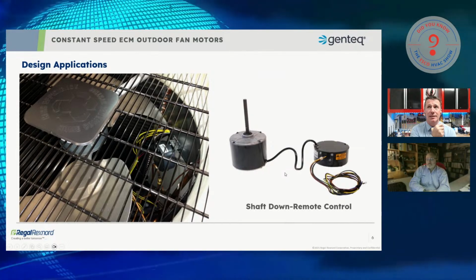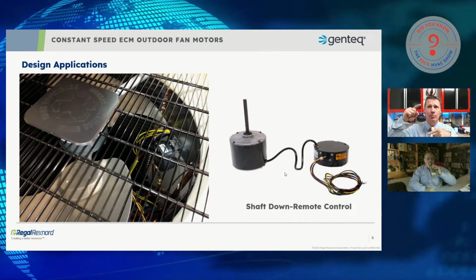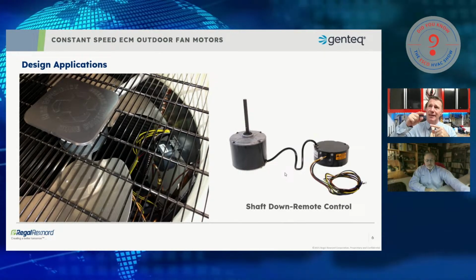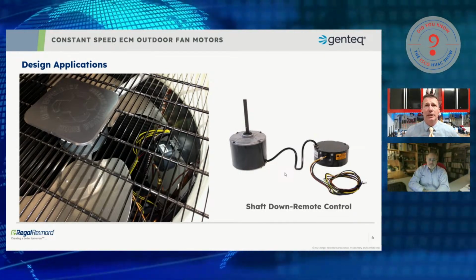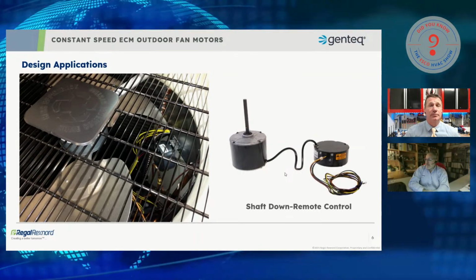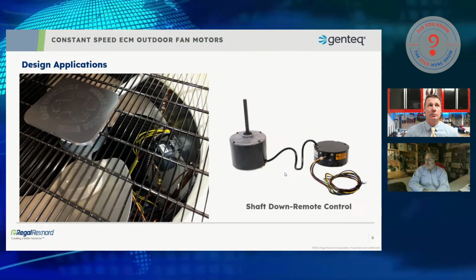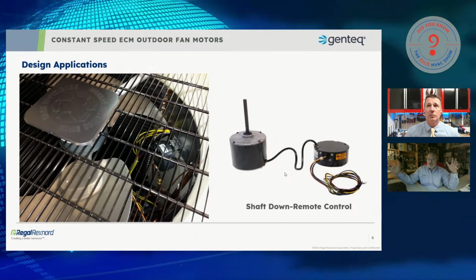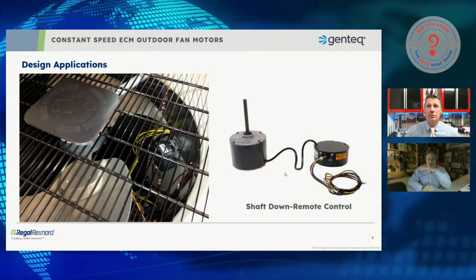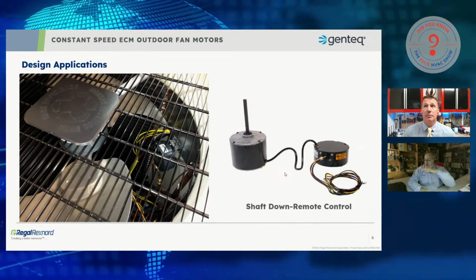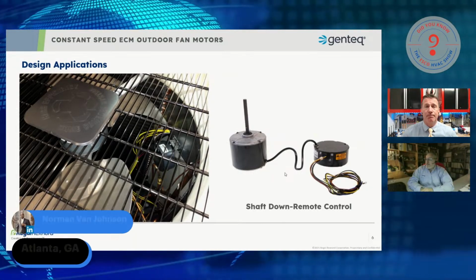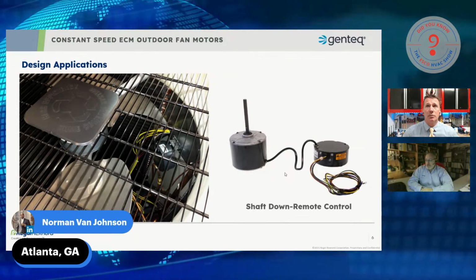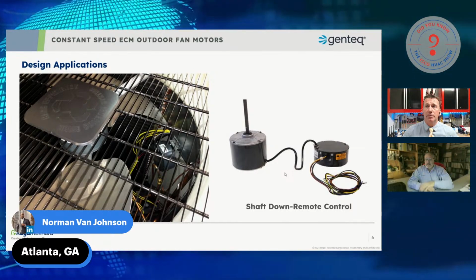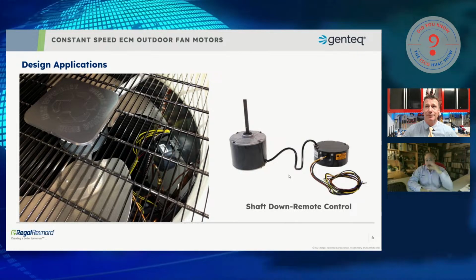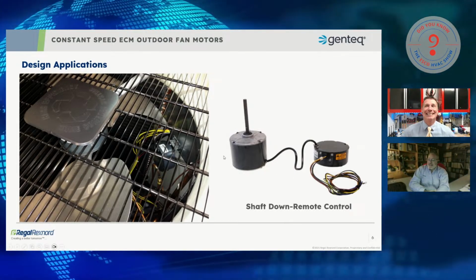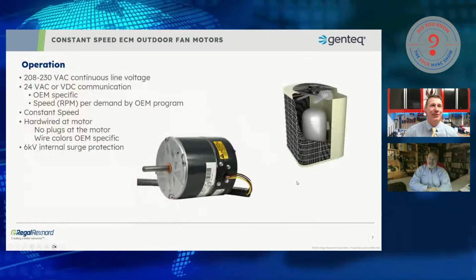Yeah, absolutely. And I have encountered these in the field, particularly on units that have a more narrow venturi on the top cover where they can't use an extended length motor. They're able to use that remotely mounted control. So they are out there. And I have plenty of speculations as to why some OEMs do and some OEMs don't. Sometimes I see these on really large systems, and I've speculated that they can't handle that extra weight out in the middle of that long expanse of cover, because it might make it bow a little bit or vibrate during operation. I used to think that it was because of distance, for clearance between the end of the shaft and the compressor, but most of these systems are taller than my car these days, so I don't think that's the case. 20 SEER, right, exactly.